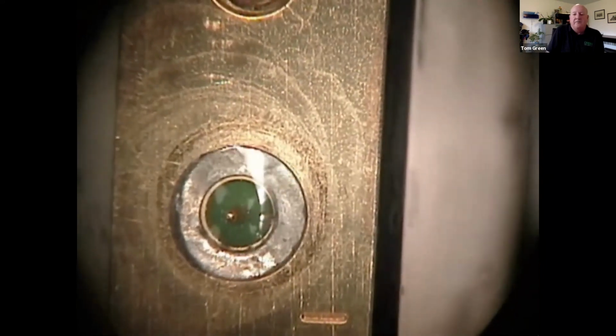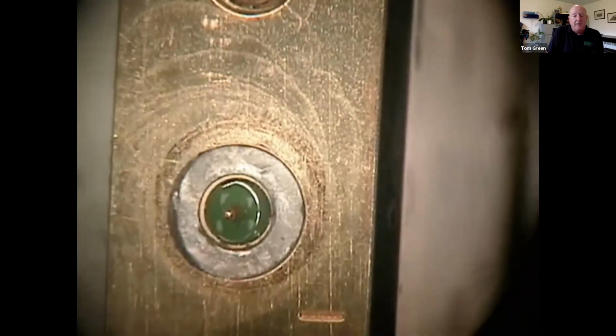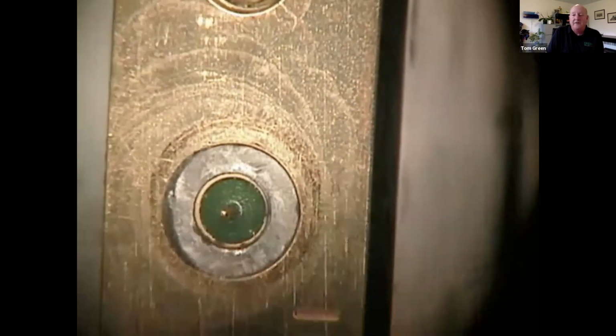But these leak paths we're talking about for fine leaks are just microscopic, and even high humidity is enough to temporarily plug them. It's just in the last 3, 4, 5 years that the community is getting used to making measurements down in the 10^-11, 10^-12 range. For years, with most leak detectors, even now with an older style leak detector in a production environment, you can't get your backgrounds much below 10^-9, maybe high 10^-10s. And now with the leak specs, if you have an air leak rate of 1 times 10^-8, depending on your bombing conditions, you're going to have to make measurements in the 10^-10s and maybe even the 10^-11s. But there's equipment out there for that.